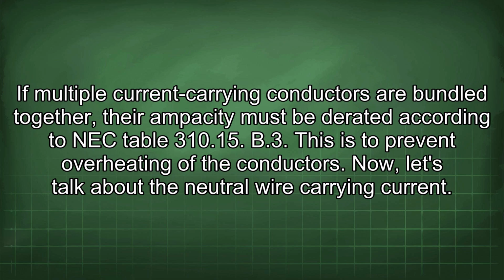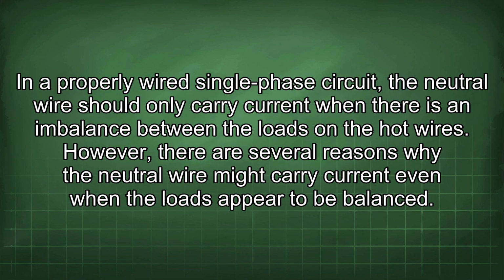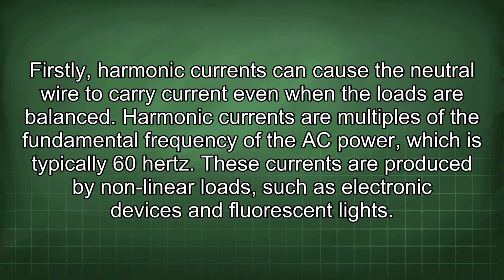Now let's talk about the neutral wire carrying current. In a properly wired single-phase circuit, the neutral wire should only carry current when there is an imbalance between the loads on the hot wires. However, there are several reasons why a neutral wire might carry current even when the loads appear to be balanced. Firstly, harmonic currents can cause the neutral wire to carry current even when the loads are balanced. Harmonic currents are multiples of the fundamental frequency of the AC power, which is typically 60 Hz.